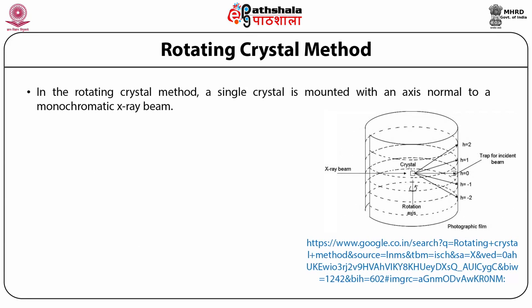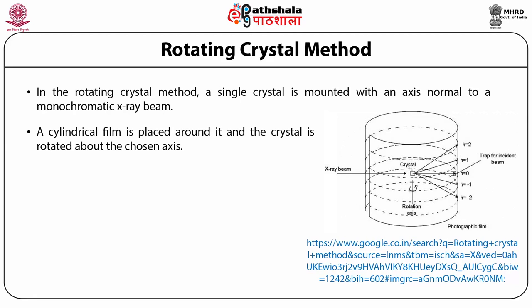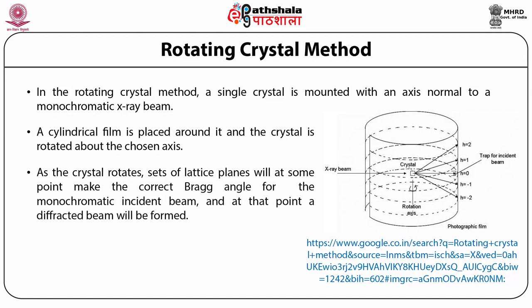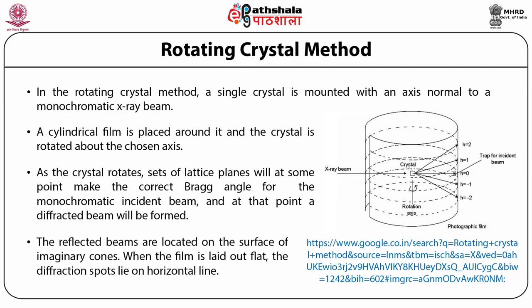The rotating crystal method: a single crystal is mounted with an axis normal to a monochromatic X-ray beam, and a cylindrical film is placed around it while the crystal is rotated about the chosen axis. As the crystal rotates, sets of lattice planes will at some point make the correct Bragg angle for the monochromatic incident beam, at which point a diffracted beam is formed. The reflected beams are located at the surface of imaginary cones; when the film is laid out flat, the diffraction spots lie on horizontal lines.